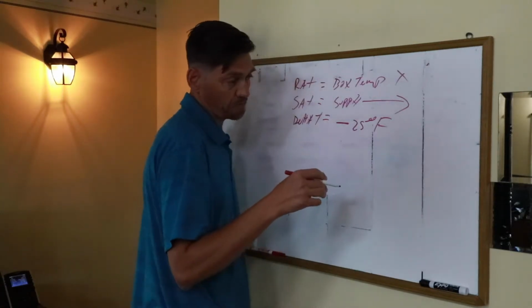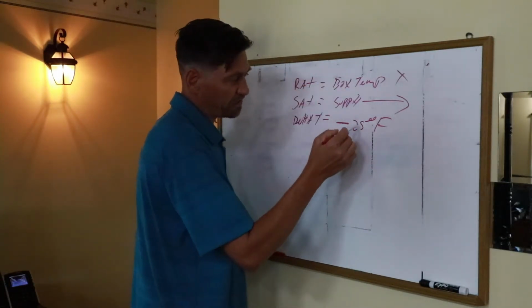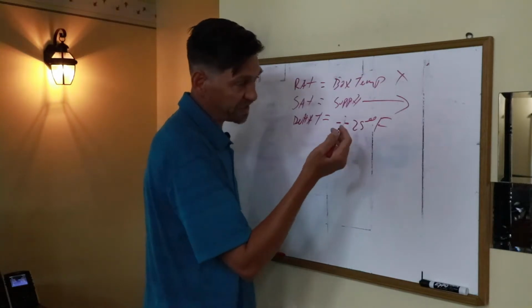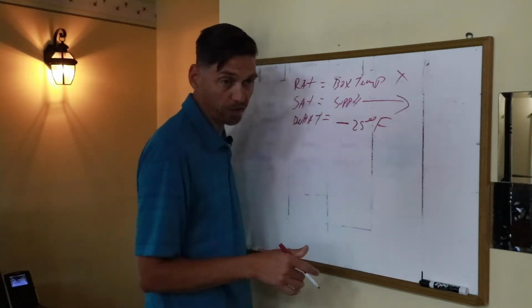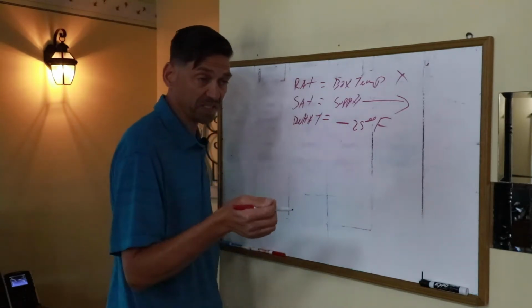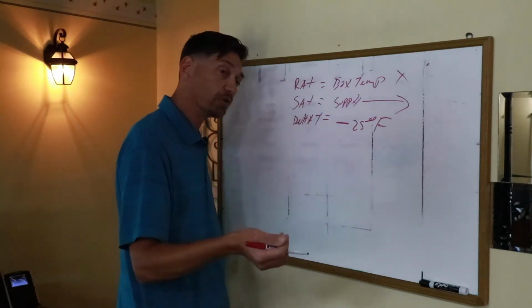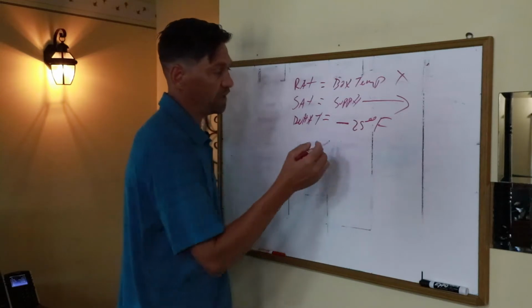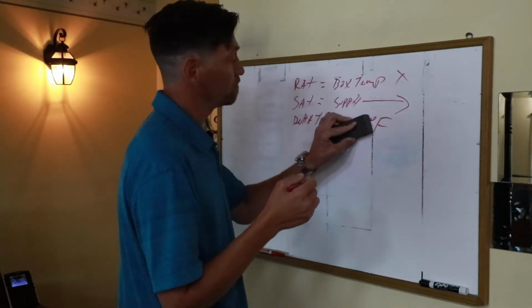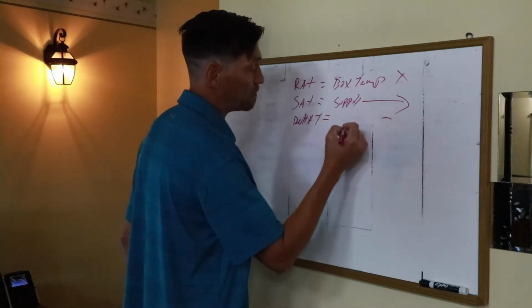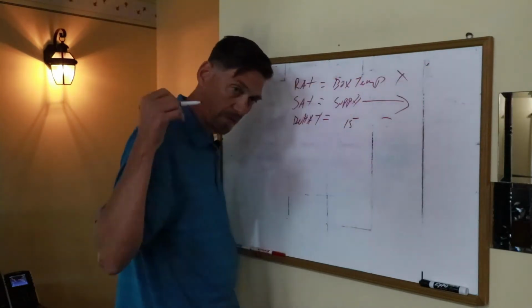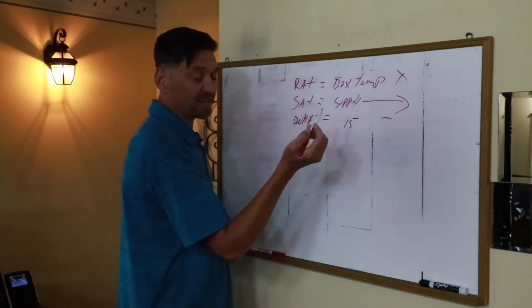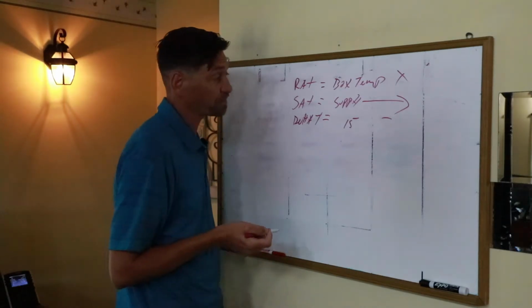And then temperatures change, and there's different things that make that number change. So if you see it's 23, don't worry about it. But it's still dropping that much colder. If it was heating, for instance, let's say it's the middle of winter and you're trying to heat a load from being frozen, then it obviously wouldn't be a minus sign. It might be just 15, which means it's warmer air going in the trailer than what's coming back to it. That tells you if the reefer's working or not.